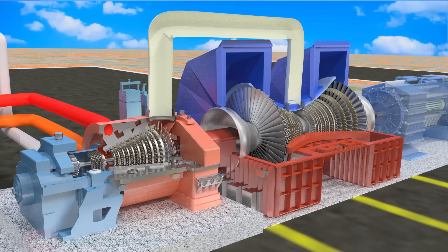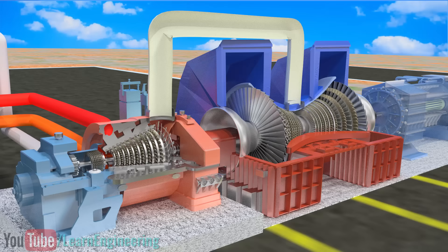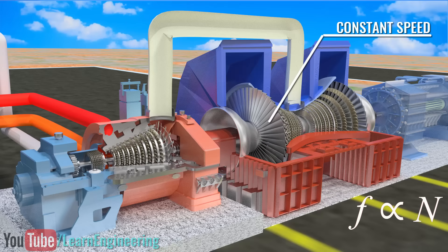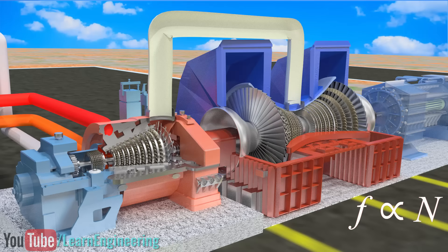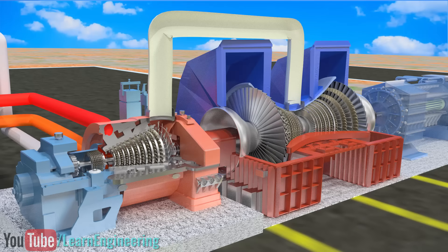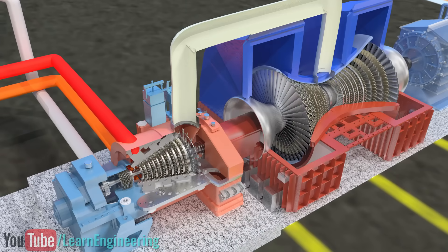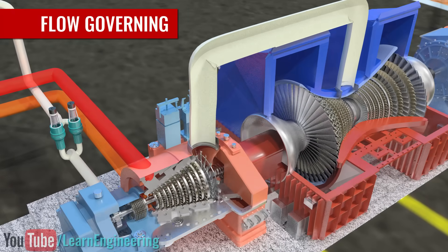One challenging problem in power plant operation is to keep the speed of the steam turbine constant. This is important since frequency of the electricity produced is directly proportional to the generator speed. However, depending on the load or power demand, the steam turbine speed will vary. To keep the steam turbine speed constant, a steam flow governing mechanism is used.